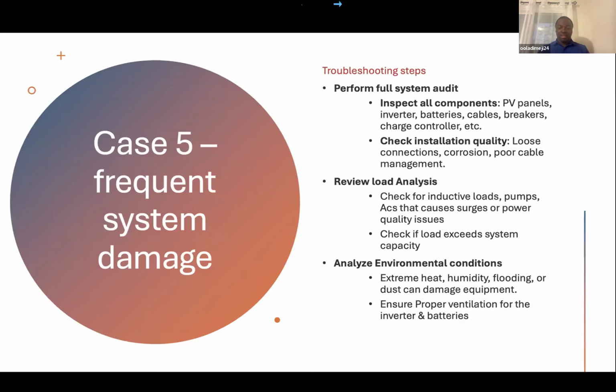Then analyze environmental conditions. Are there extreme heats in your powerhouse, humidity, flooding, dust? Sometimes, from my experience, dust in a location can cause an inverter especially to go bad frequently, because the boards in the inverter are covered with dust every time, and they cause short circuits on the board and they go bad. So as little as dust can cause damage to your equipment. Then ensure proper ventilation for inverter and batteries.